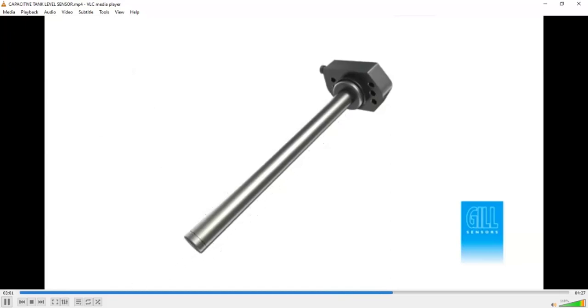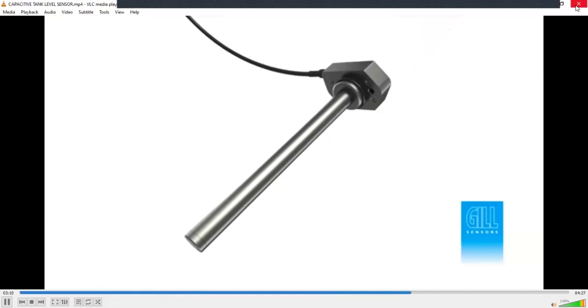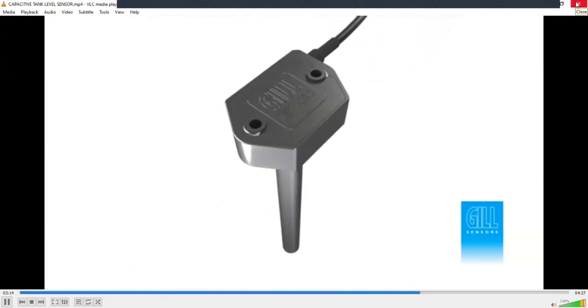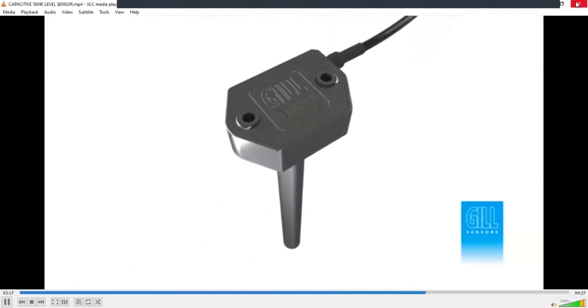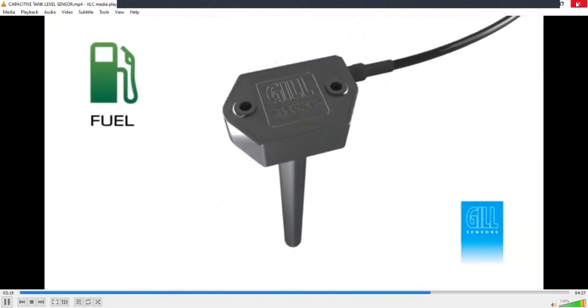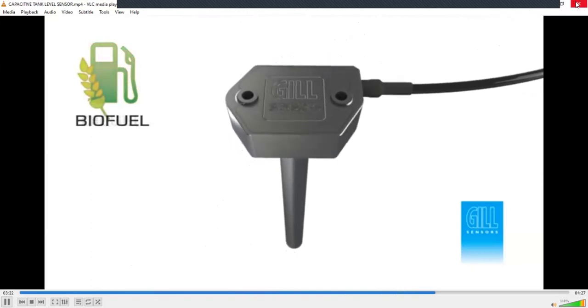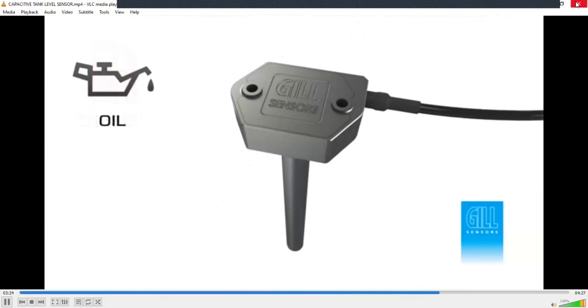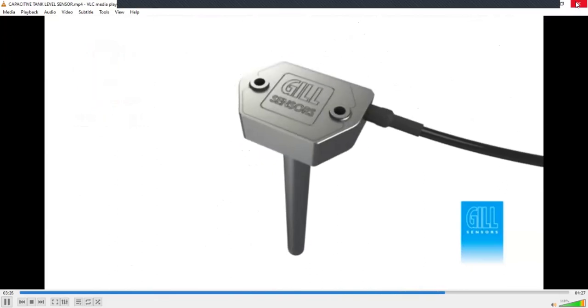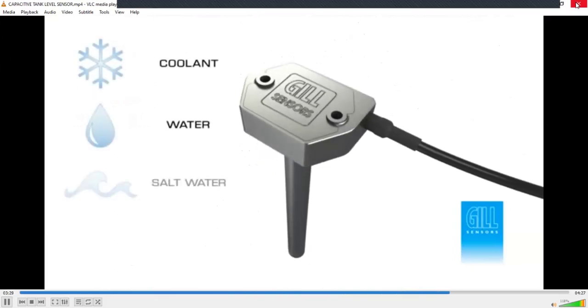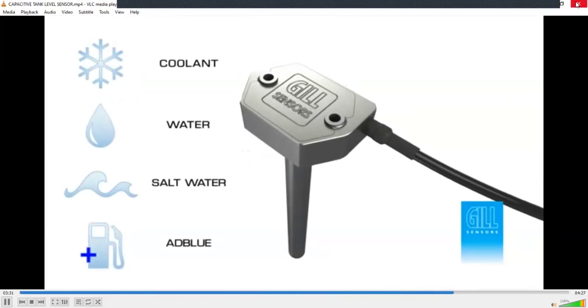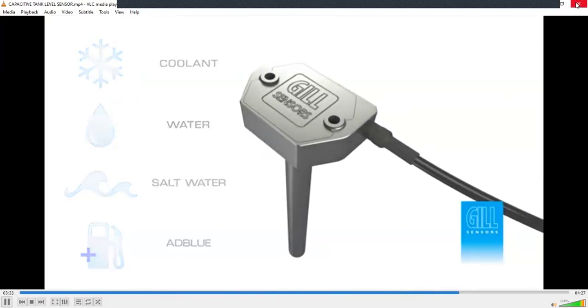Dielectric fluctuation caused by temperature variation is managed using offset values also stored within the sensor memory. These values are typically applied during factory calibration at Gill Sensors. A wide range of fluids can be measured using a Gill liquid level sensor, including fuels, biofuels, diesel, and oil, and by modifying internal components, the liquid level of electrically conductive substances, such as water, can be measured.